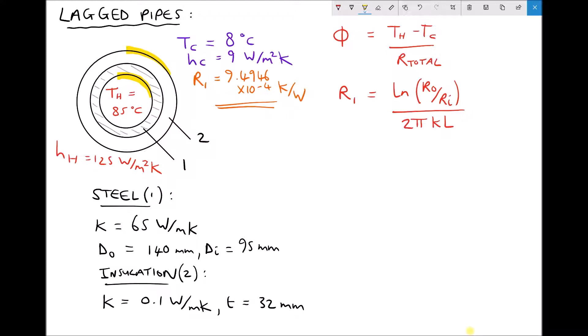We've specified a surface heat transfer coefficient of 125 watts per meter squared Kelvin for the inside surface of the pipe, and a value of 9 watts per meter squared per Kelvin for the outside of the insulation. These values are primarily affected by whether the fluid at the boundary is moving. We have a very high surface heat transfer coefficient for the fluid flowing through the pipe because we're assuming the velocity is relatively high, whereas the air on the outside we're assuming has very little movement.